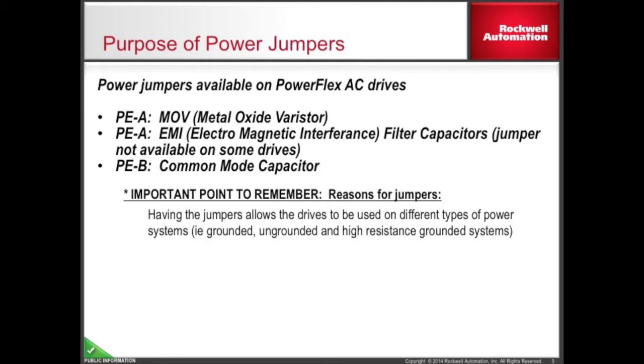There are typically two power jumpers labeled PEA and PEB. The PEA jumper is associated with the MOV or Metal Oxide Varistor provided on the drive. In some frame sizes, it is also associated with the installation of the EMI filter capacitors. The PEB jumper is always associated with providing a ground path with the common mode capacitors. The remainder of this video will help you understand the purpose of these devices and when it is appropriate to install the jumpers associated with these devices.